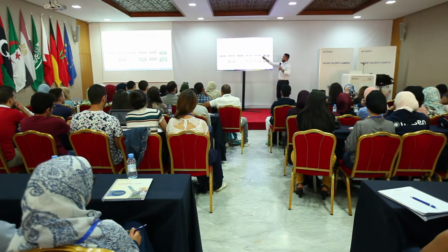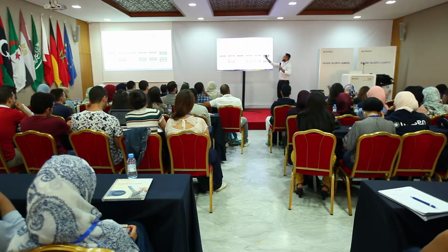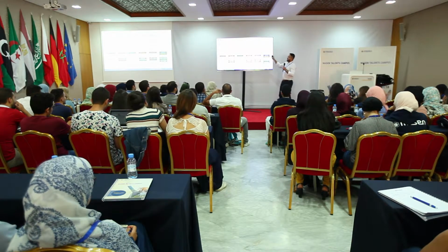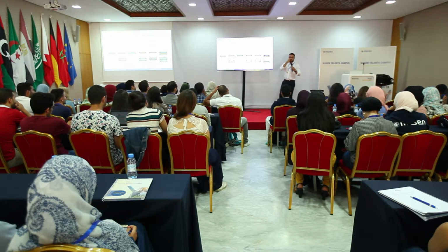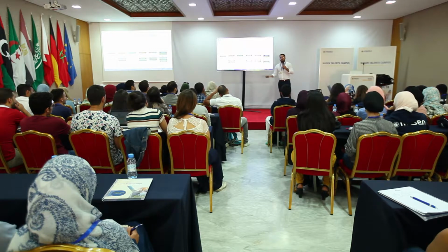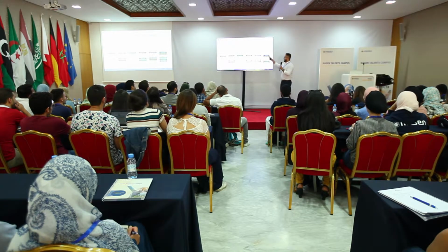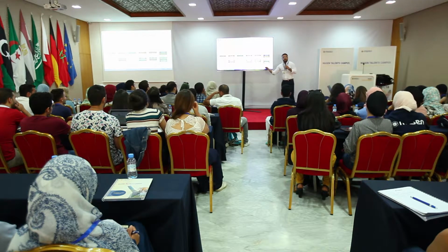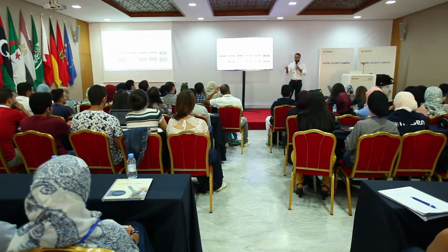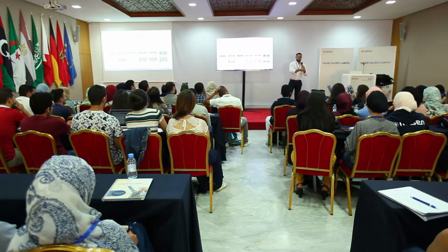Whereas in a CSP plant, the capacity factor could be 80%. It depends, like you saw before in the image I showed you from real data. The plant was operating at all times because we had storage. So this is a measure that I can quantify and I could build the trade-offs: how much more it costs to have a plant with a higher capacity factor, or how much more I need to invest. And it could be an objective, something I can quantify.